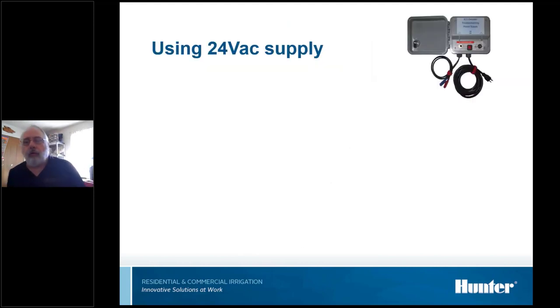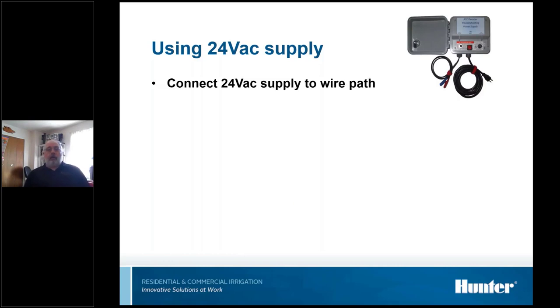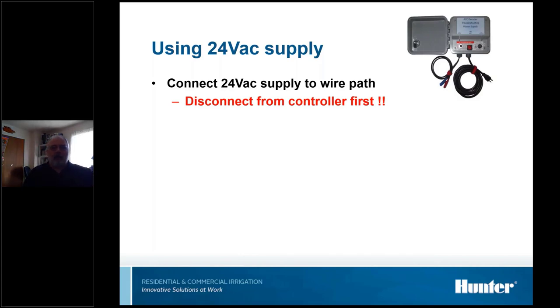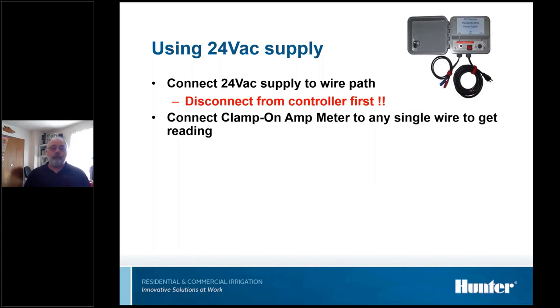So now if you do happen to have a 24-volt power supply, what we do is we're going to disconnect the wire path from the controller and hook it up to the transformer, turn 24 volts on, and then we can use the clamp-on amp probe. Do not connect the 24-volt transformer to the controller unless you want to buy a new controller. And we're just going to connect the 24 volts to the wire path, and we're going to use the amp meter to get a read.